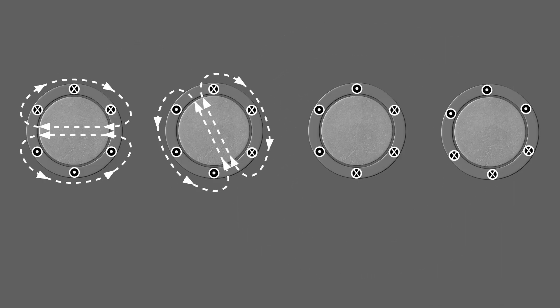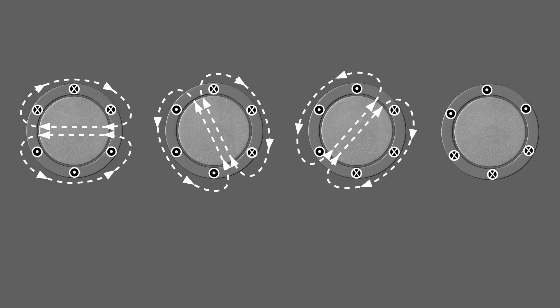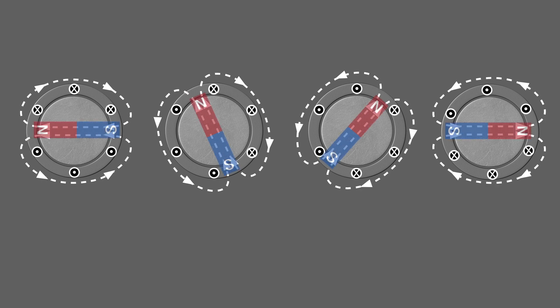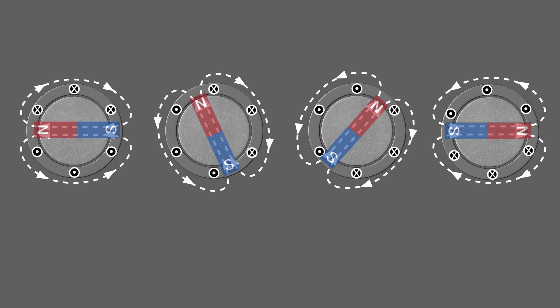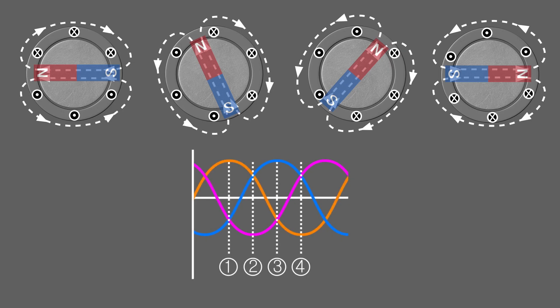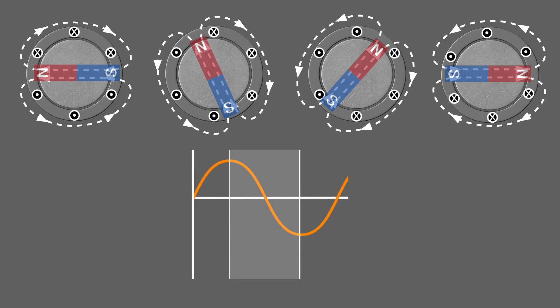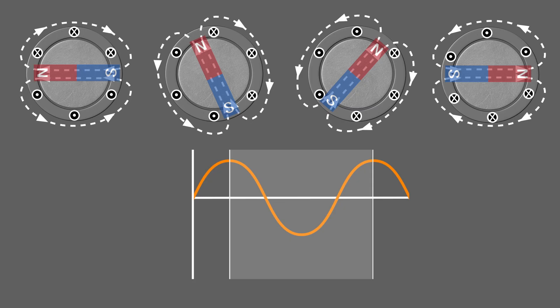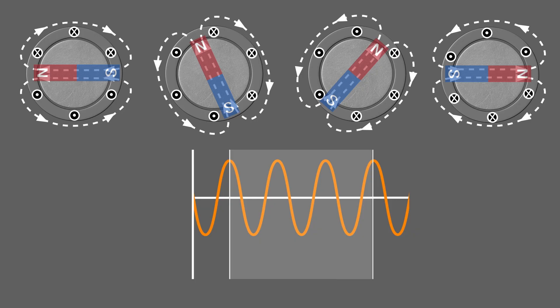In section 2, the magnetic field is generated like this, in section 3 it goes like this, and in section 4 a magnetic field is created like this — it looks as if a magnet is rotating. When a rotating magnetic field is created this way, the disc will rotate along with it. From section 1 to section 4, the magnet rotated for half a turn. Since half a cycle of the waveform has passed, half a turn has been made. After one full cycle of the waveform, the magnet will turn one full cycle too. Increasing the frequency will increase the speed of the rotation.